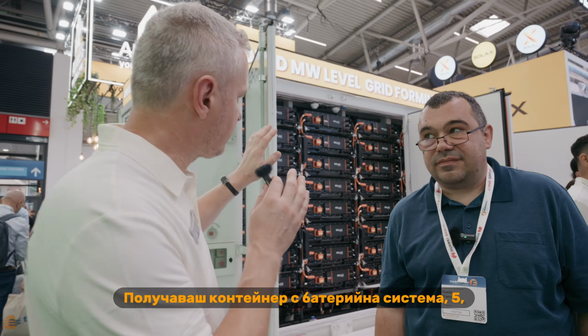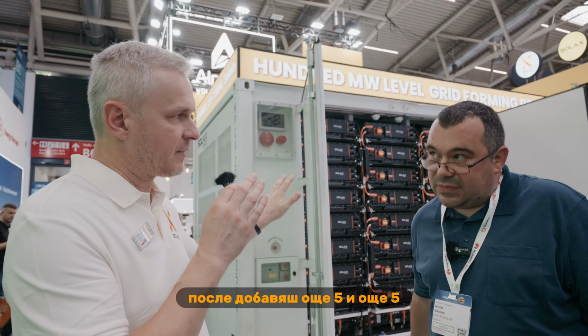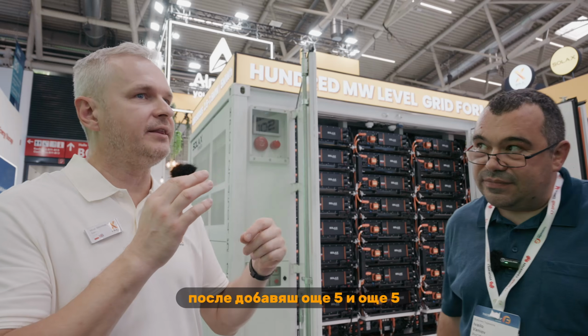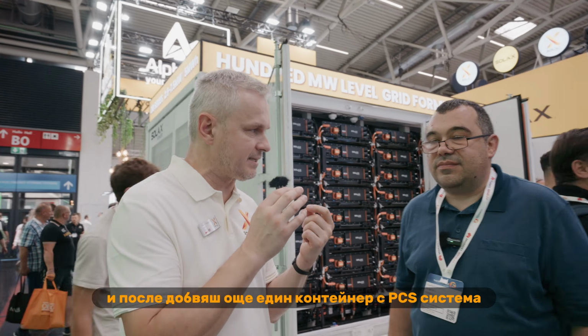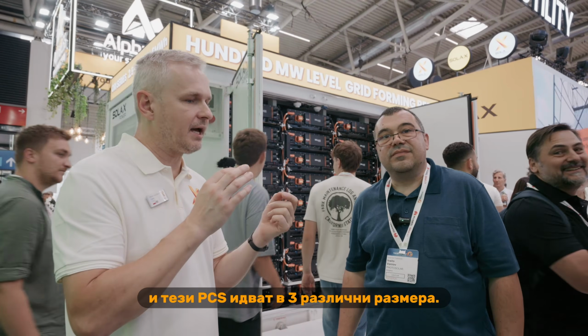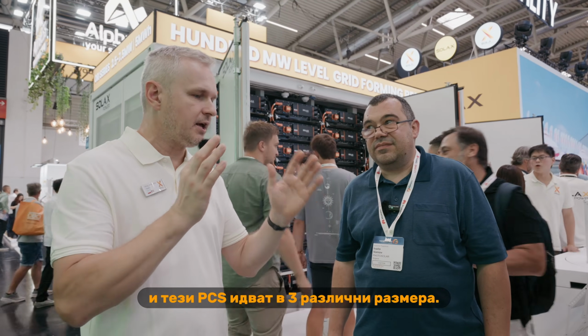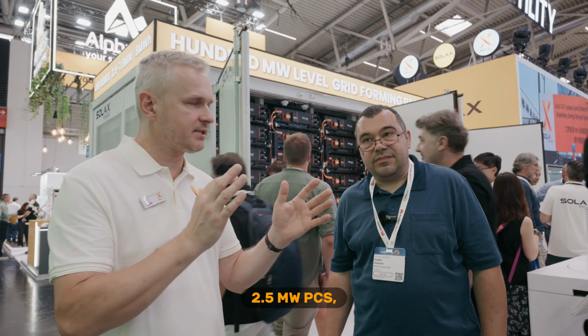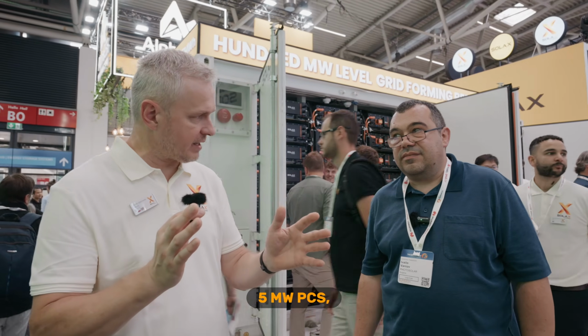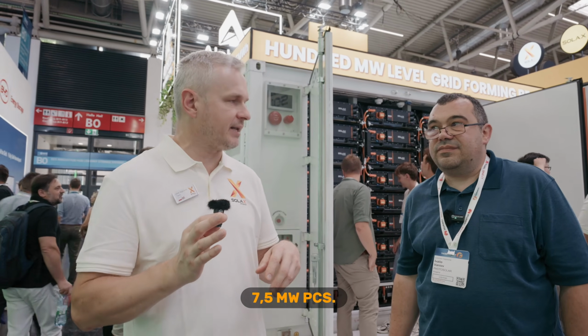So you're getting a container with a battery system, 5 megawatt hours, then adding another 5, another 5, and then you're getting another container with a PCS system. Those PCSs can come in 3 different sizes: 2.5 megawatts, 5 megawatts, and 7.5 megawatts.